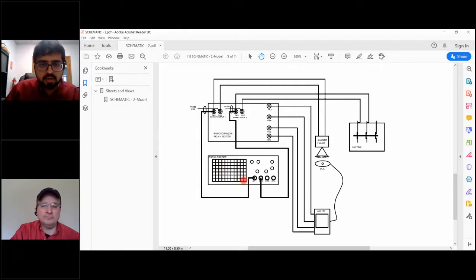What we see on the oscilloscope: channel 1, we apply a voltage across one of the phases of the quencher. That's probe 1, which is measuring the voltage across the phases. And probe 2 is when we trigger the flash. We trigger the flash using the tester itself. We set up a state sequence on the relay test software to inject current and flash at the same time simultaneously. So that's how that's done.